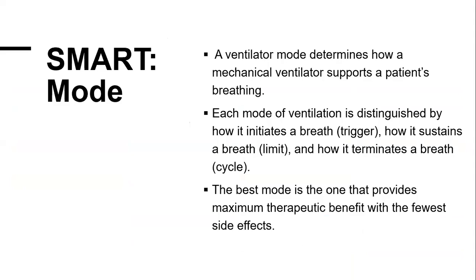Now the second thing we need to talk about in smart ventilation is the mode. What is a ventilator mode? This is what determines how the ventilator supports your patient. Each mode of ventilation is distinguished by how it initiates a breath, how it sustains a breath, and how it terminates a breath. When we're talking about cycling, we're talking about changing from inspiration to expiration. So the mode of the ventilator can be distinguished based on these parameters.